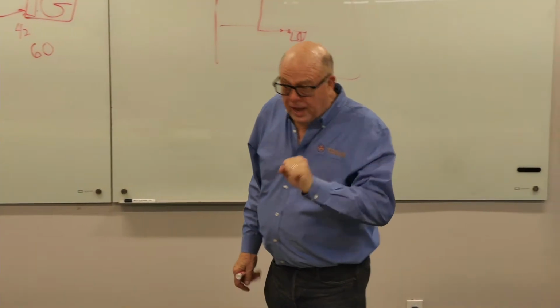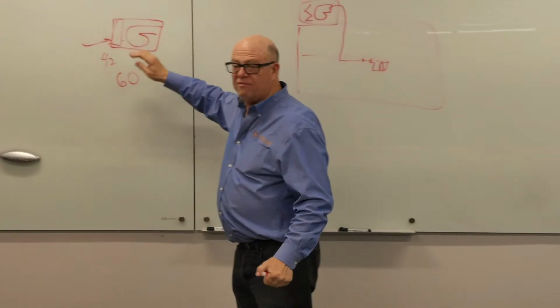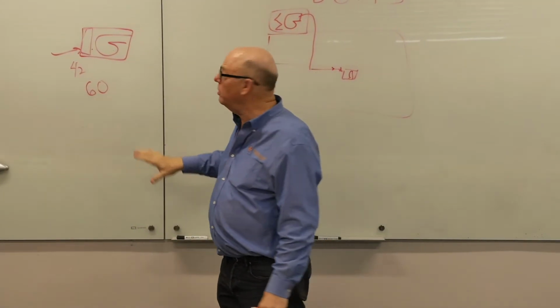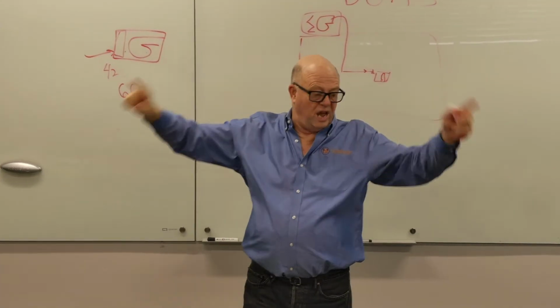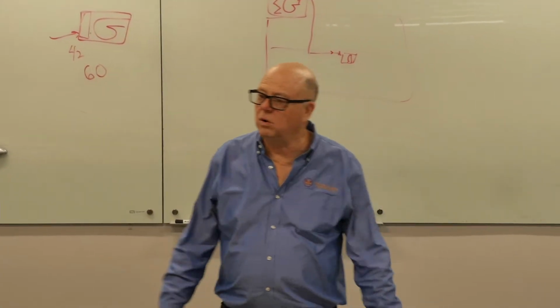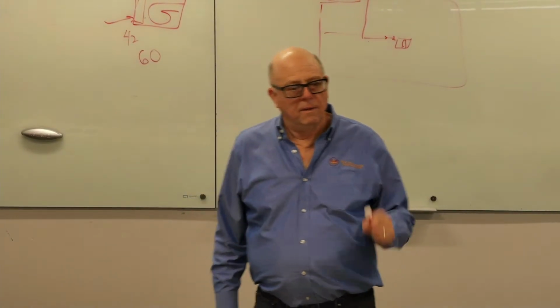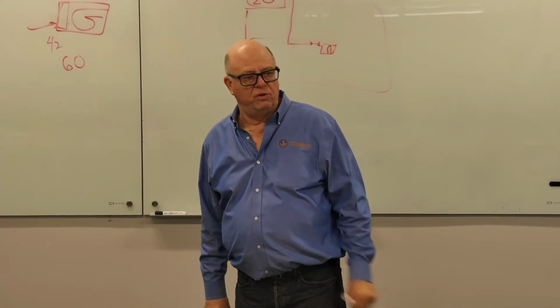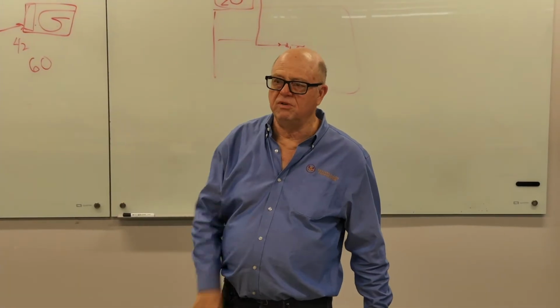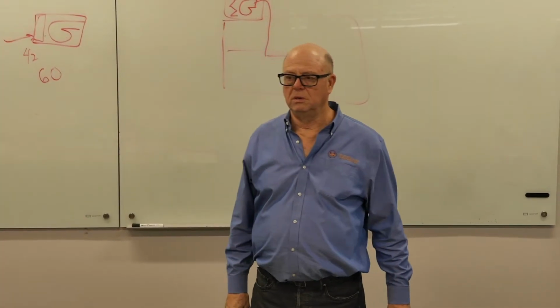What we did about that, and I veered off, but it'll get us back to the DOAS conversation. What we did about that is there's 16 fan coils in the building. VRF has what's called a dehumidification mode, and you can pop it into full cooling, and that's what it'll do.